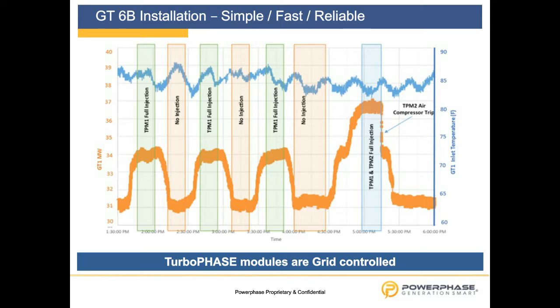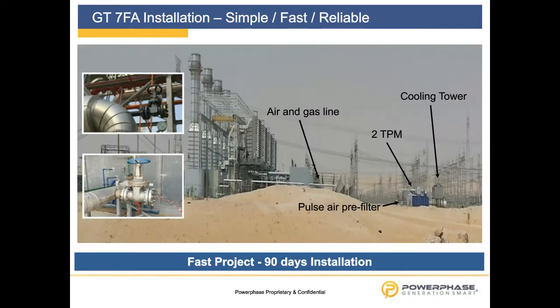In the next slide, I want to show you an installation in the Middle East, which was a fast-track installation to cover summer peak. We have the 2 Turbophase modules, a pulse air pre-filter as there were desert conditions, and our self-sufficient cooling system. Then we see a long gas line into the gas turbine compressor discharge manifolds, around 250 meters away from where the air is actually injected in the gas turbine. That project was done within 90 days, and it was done in time.